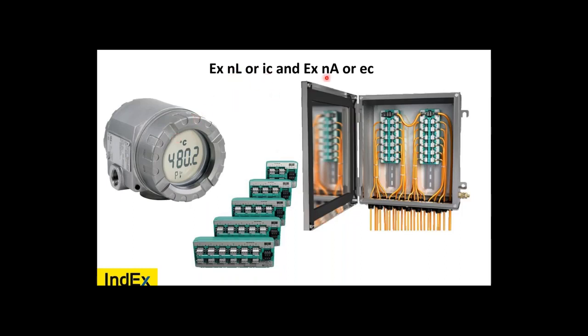Basically, with these 4 different protection techniques, depending on the year of installation or manufacturing, you have a multitude of options altogether. If you see an EXNA certified terminal like this, let me tell you something, it must go into an NA enclosure, IP54 minimum.